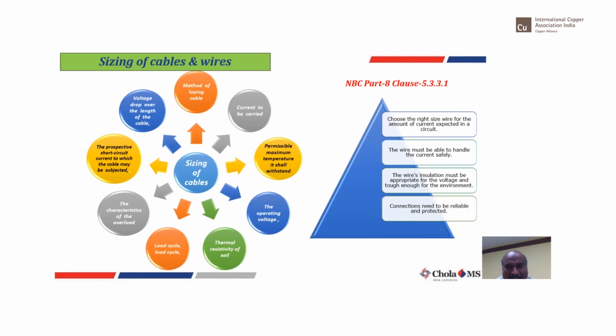If you have laid it on a cable tray, it is different. If you have laid it underground, covered with soil, then the capacity is different because there is a little bit of cooling, and the percentage of loading also matters. So the sizing will depend upon all these parameters: the method of laying the cable, how much current is to be carried, the permissible maximum temperature it shall withstand because there are derating factors by the OEMs, the operating voltage, thermal resistivity of soil, load cycles, characteristics of overload, short circuit protection levels, and voltage drop, from where the source is to where the last building of the plant is, meaning how long the cable length is. All these things play a role while sizing the cable.